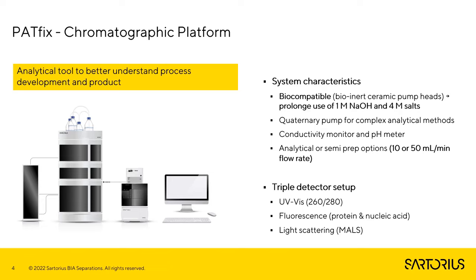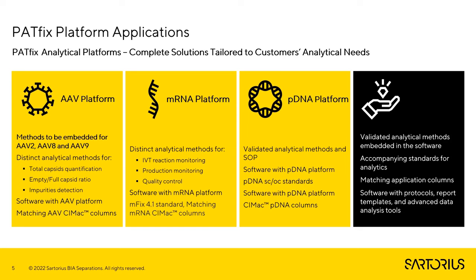The detector setup that is primarily optimized for AAV applications is UV 260/280, fluorescence, and a light scattering detector. Fluorescence provides native protein detection or nucleic acid detection when the sample is dyed with PicoGreen. This triple combination provides the most detailed information that we can obtain in one run.